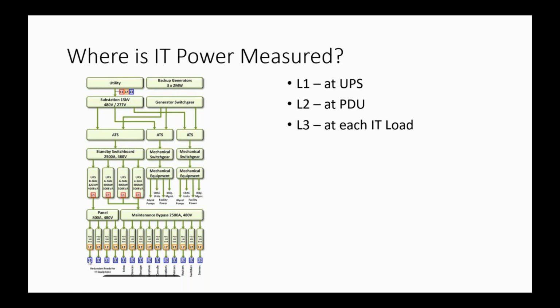Because we're not going to be able to wait until every single device has L3 level coverage at the device level. We're going to want to make some buckets out of those things and say, okay, I can't get you the data at those mechanical switchgears, but I can take the measurements upstream from that, and then at least I can categorize and define it.